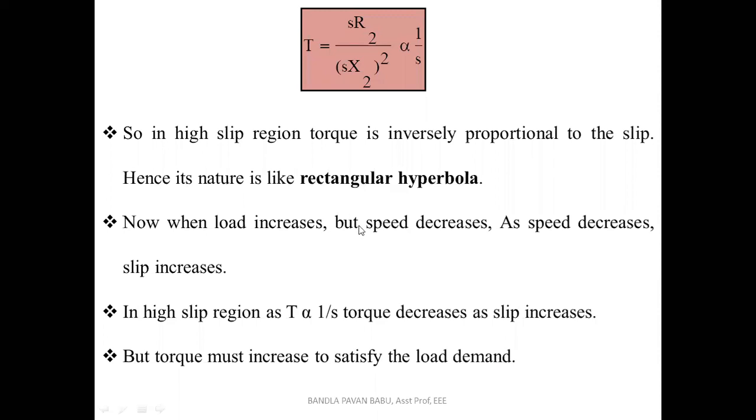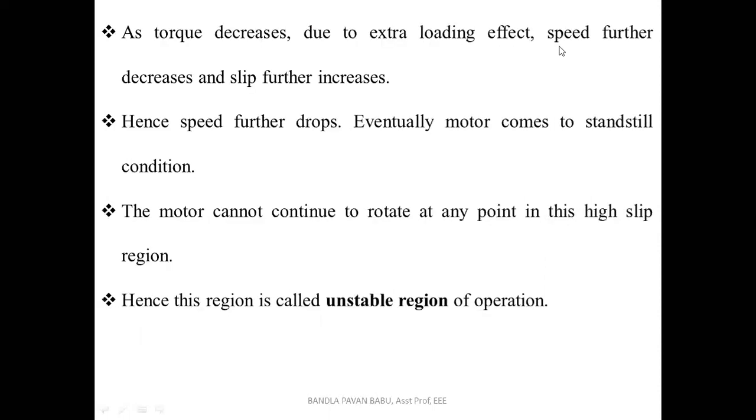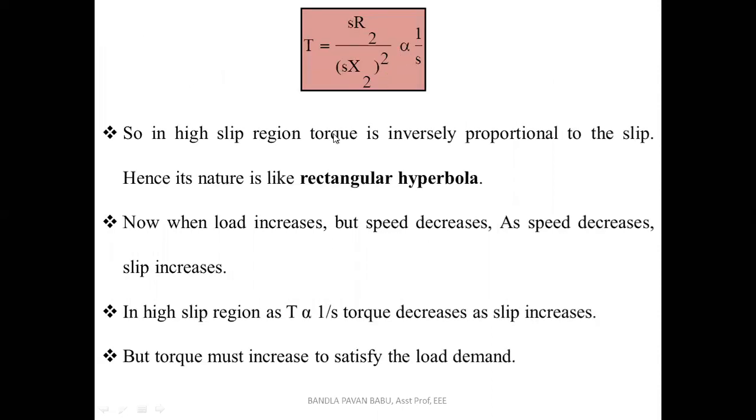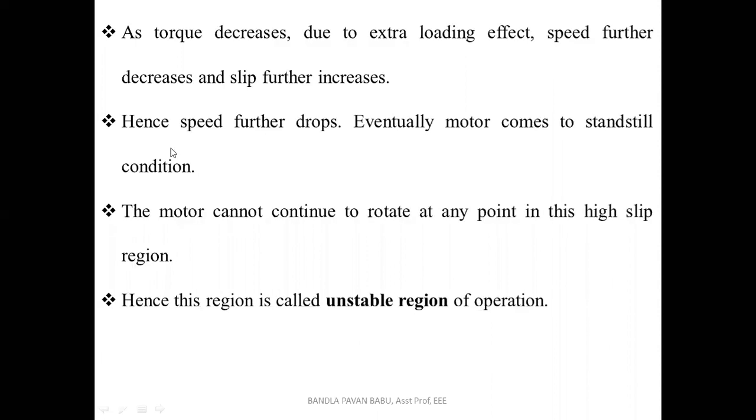So if it fails to reach the demanded mechanical load, which requires a desired speed, what happens if we keep on increasing the loading effect? The speed further decreases and the slip further increases. Since the speed is getting reduced, obviously the slip further increases. If there is an increase in the slip, what happens? The torque will be reduced. Hence speed further drops, and eventually the motor comes to standstill.